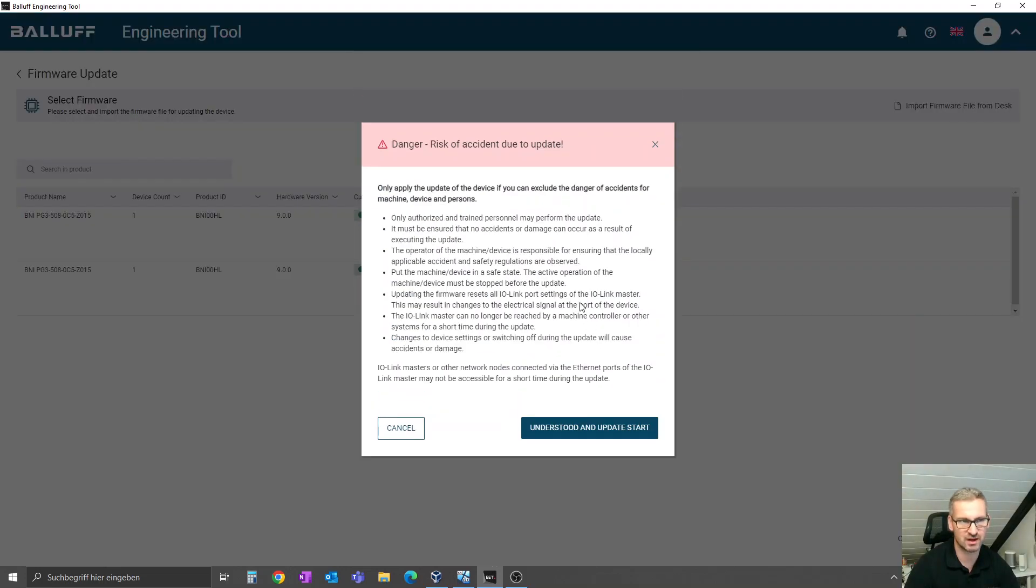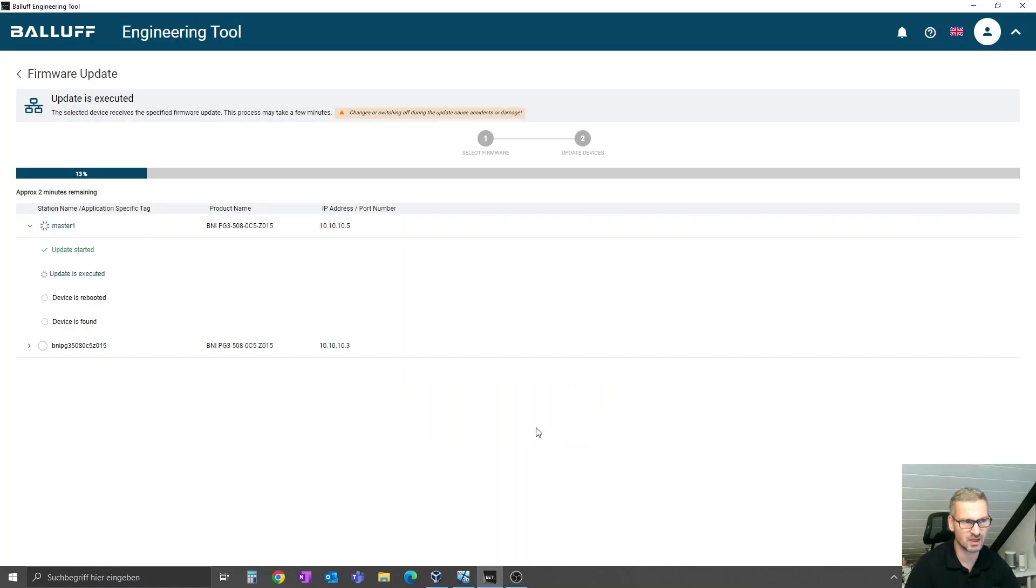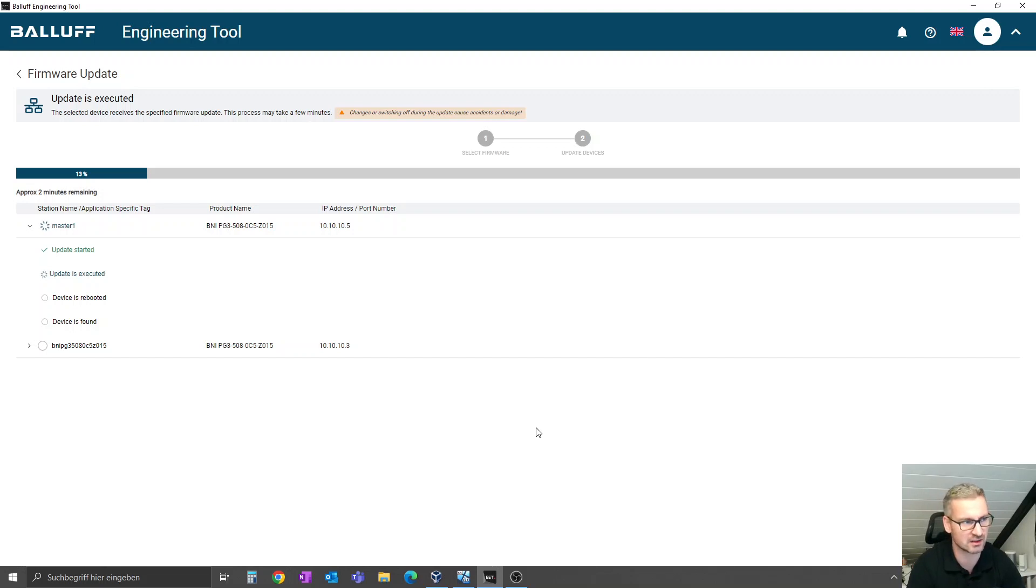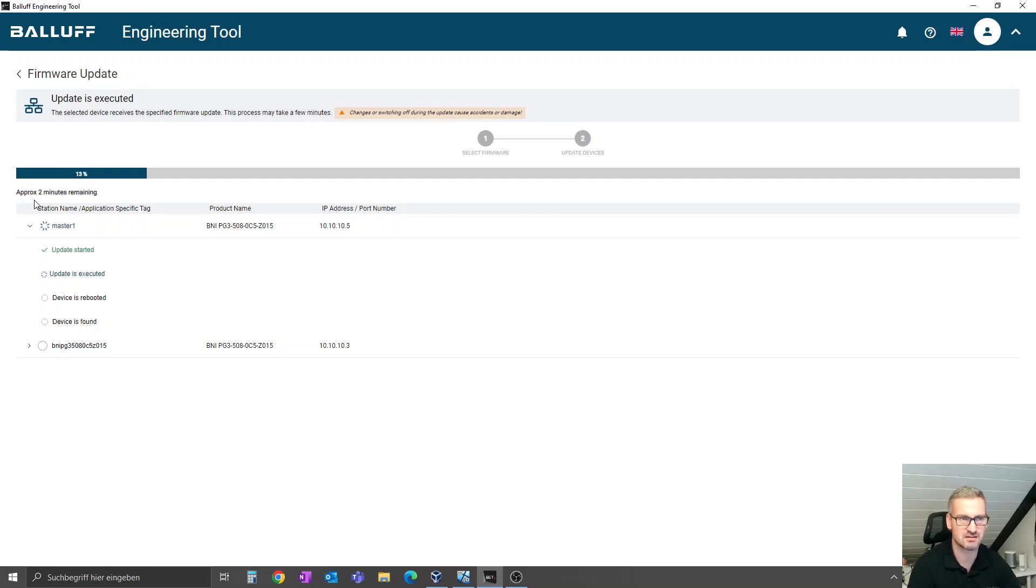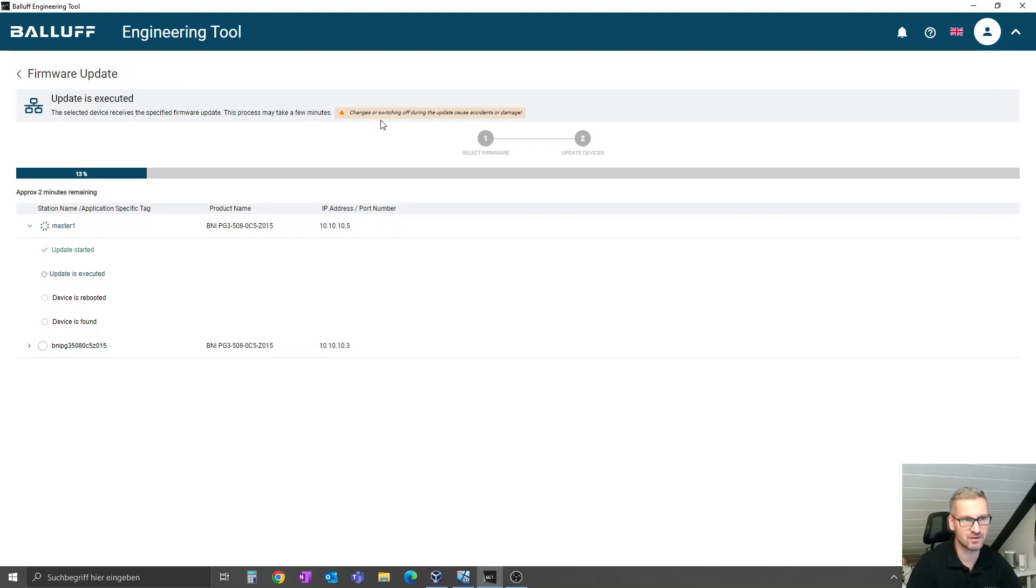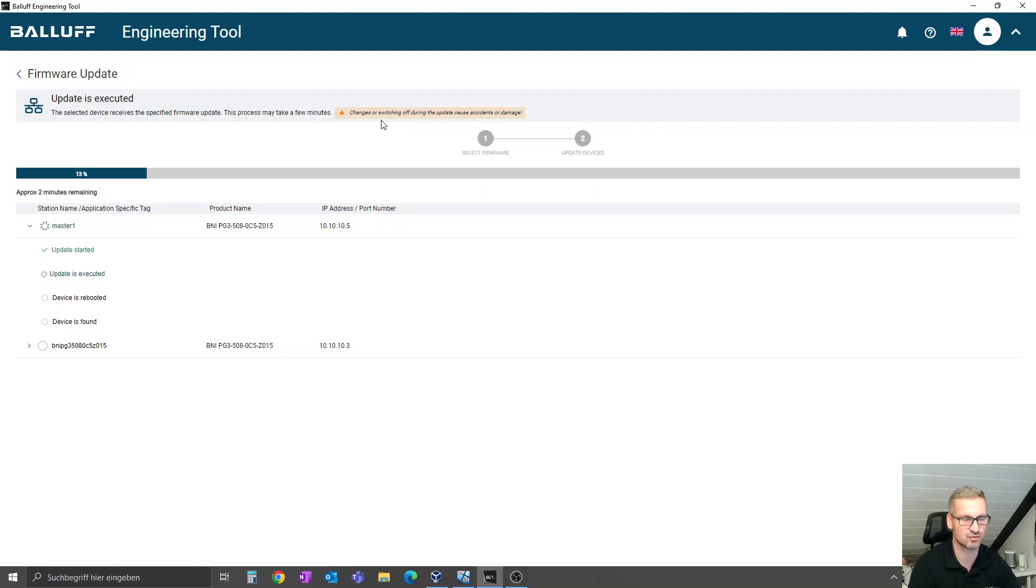Click on the right side update device, accept this notification, and then the update process will start. You see here approximately two minutes remaining to finish up the process. Now it uploads the firmware file to the master, starts the update process, makes a double restart, and then the device is updated. If you make this firmware update, please do not switch off the power or the network communication to the device. This is really important; otherwise, your update process will fail.